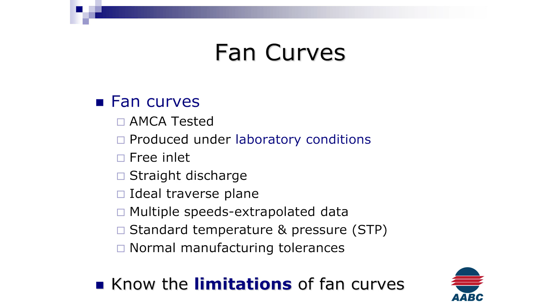Standard temperatures and pressure, and normal manufacturing tolerances. That goes back into tip speed. When we have to increase fans, we find them deficient in the field. We've got to speed them up. We're limited by brake horsepower and tip speed of the fan. The last thing we want to do is speed a fan up that could actually fly apart because the welds are not rated for that speed. So it's really important to know what is going into that fan curve and how they found it. And knowing the limitation of the fan curve is super important.